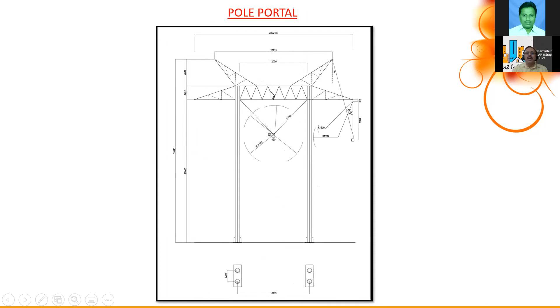Right of way required: you can see pole portal right of way is 66 meters, whereas the triple V configuration is only 56 meters. Right of way means we have to pay compensation, but in India, unfortunately, the compensation is very less compared to foreign countries. That's why abroad, people go for less right of way.